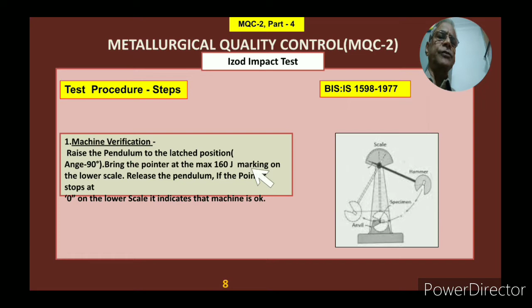Then the first step was this. Then the second step, raise the pendulum to the latched position. You now have to raise this up to 90 degree. Then the third is to fix the test piece with the notch facing the pendulum movement. Accordingly you have to fix the notches, positioning the notch with the help of a positioning gauge. You have to use a positioning gauge, and accordingly position the notch. This is very important, and quite meaningful because you have to maintain this.